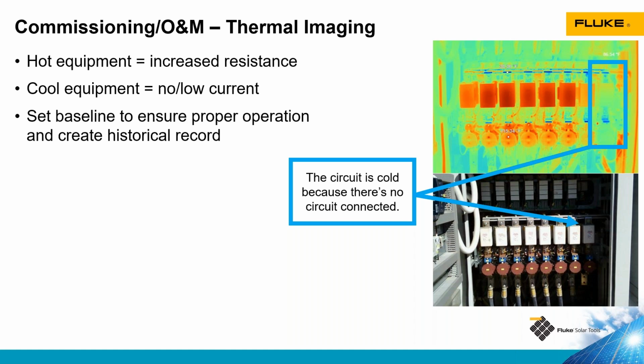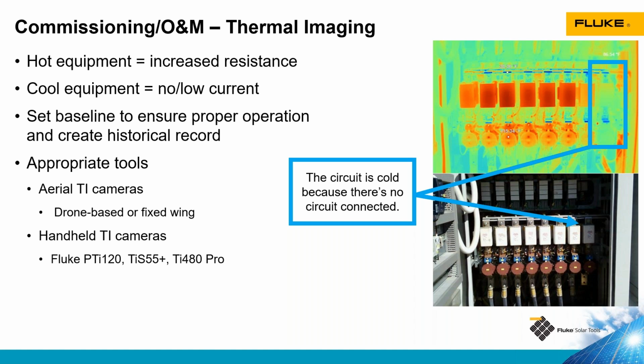At commissioning, we can use thermal imaging to create a baseline and a historic record so that we can review that later and see how things change over time. Although with thermal imaging, it's not always easy to compare things at different times because the ambient temperature might change, humidity might change. There are many things that affect those pictures.